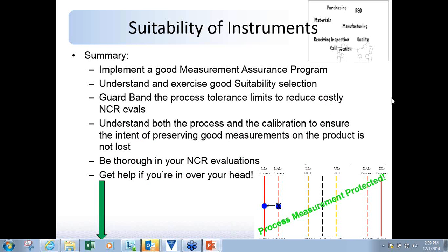So to summarize, for suitability of instruments, implement a good measurement assurance program that covers not just the selection of the right tool for the job, but using it correctly, storing it correctly, having the right environment, all of those things. So understand good suitability selection, going through the parameters and process accuracy ratios. Document that if you need to support why you selected the right instrument. And for replacement of that instrument in the future, you'd want to go through the same process. If you ever changed your process tolerances down the road for whatever reason, you'd want to go back and reevaluate the instruments that were selected for the job to make sure they're still suitable.